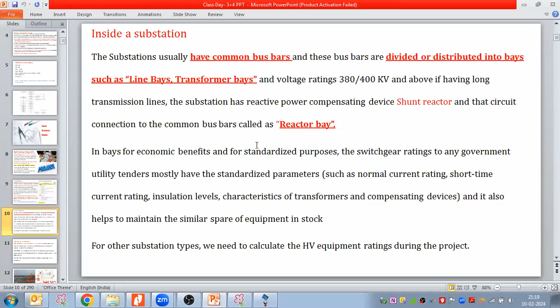This is called a shunt reactor, and the bay or circuit which connects the reactor to the bus bar, we call the reactor bay. So bay means it represents a circuit connection in a substation. If I'm connecting a line circuit to the substation, I'll call that circuit the line bay. If I'm connecting a transformer circuit to a bus bar, that connection we will call the transformer bay. So that's all we discussed.